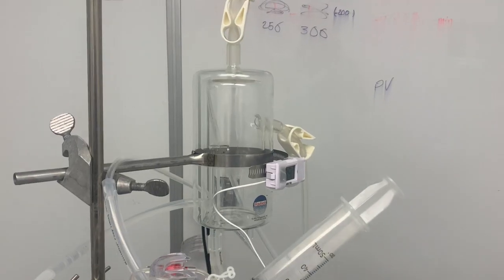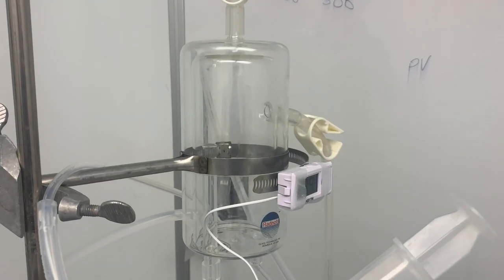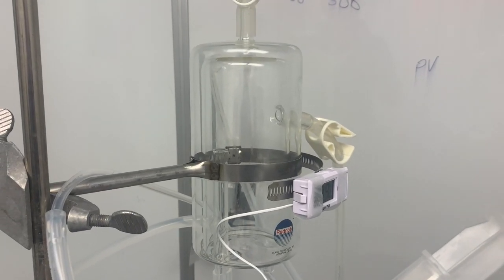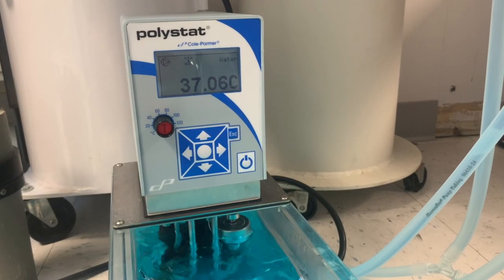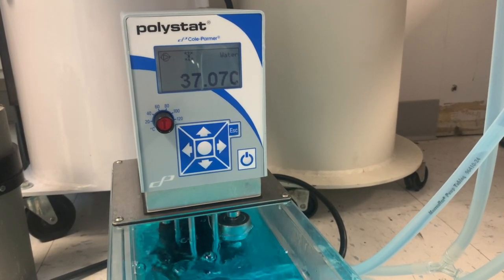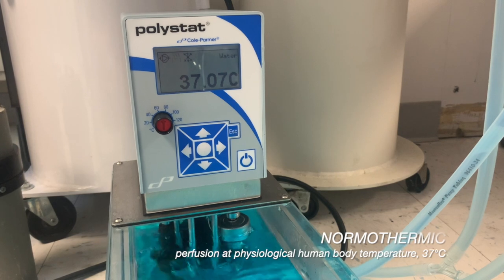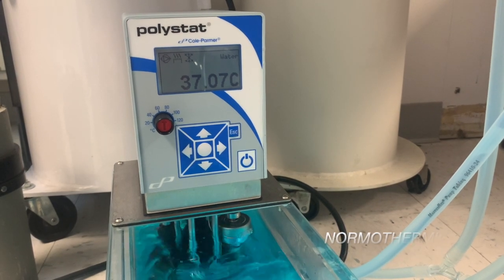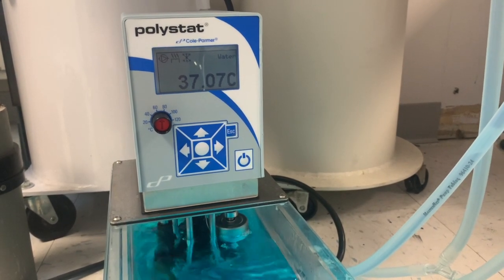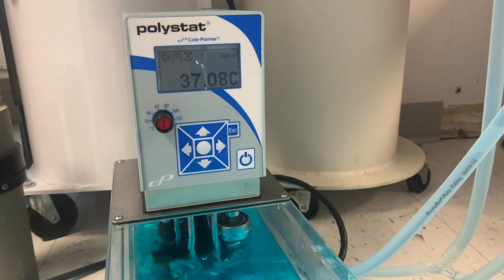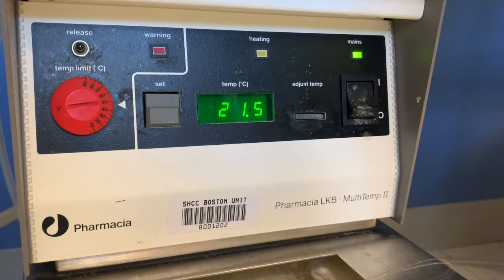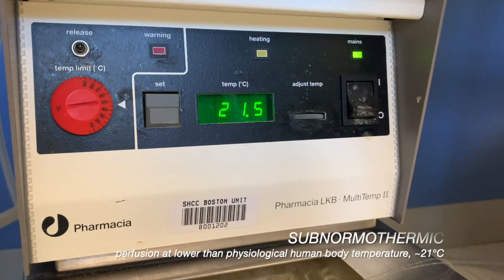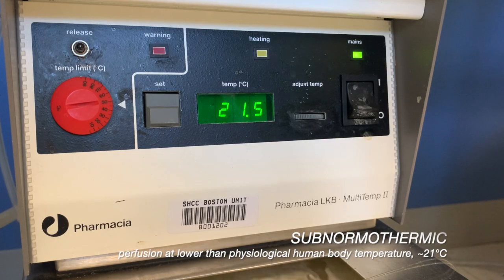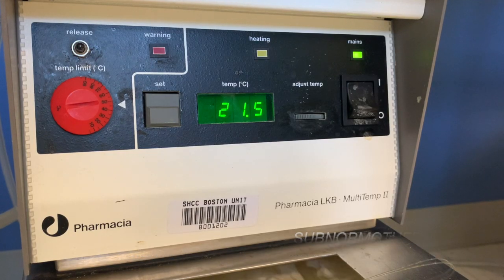All of the glass components of the system are double-walled to run temperature-controlled water through the system. For normothermic machine perfusions, we set the temperature to 37 degrees Celsius. This is to mimic normal body temperature so that the metabolism is maintained at physiological rates. To reduce the metabolism, the chiller can be set to different temperatures, such as 21 degrees Celsius or even lower.